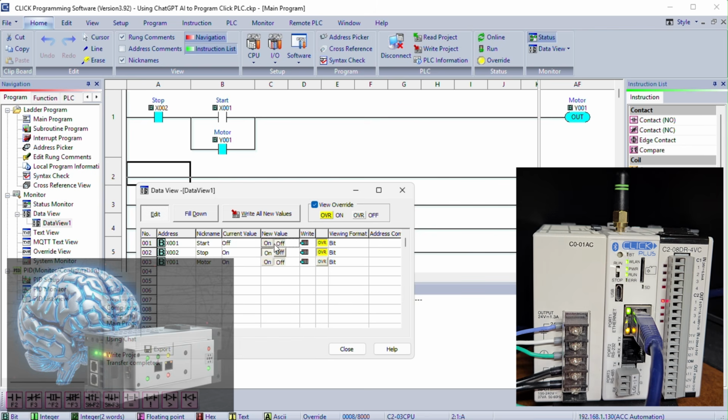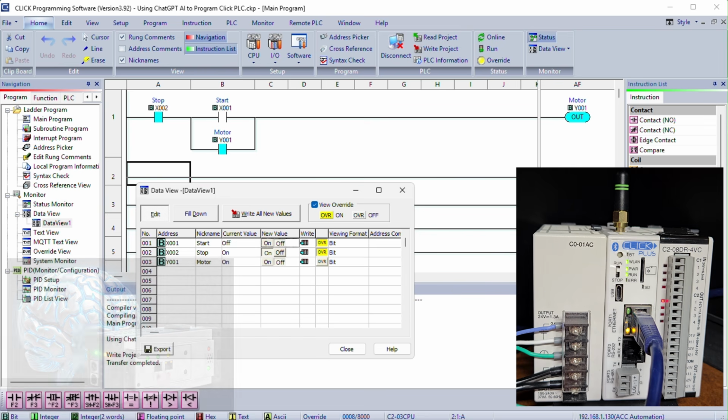First, I ask the AI to explain the rung back to me in plain English, and I check it against what I know about my wiring. Second, I test it on the PLC with the field wiring off, forcing the bits in Data View and watching the output before it controls a real motor. The AI is a fast helper, but you are the safety check that never changes.